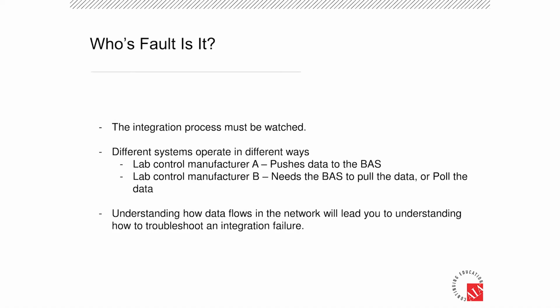The reason is control systems are all different on how they move data. Lab control manufacturer A, trying to be generic here, worked on a laboratory system where their local lab control server pushes data out to the building automation system. So if data is stale, not refreshing, or dropping out, in that instance it's not the control vendor's fault, it's the lab control vendor's equipment that needs to be addressed to find out why data isn't being pushed out. Something's wrong on their server.